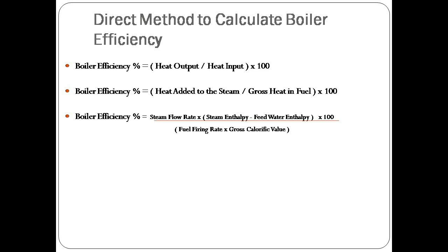As you can see in the third formula, by multiplying steam flow rate with the difference of steam enthalpy and water enthalpy you can calculate heat added to the steam. The gross heat present in fuel or whatever we are supplying to boiler is simply the fuel firing rate multiplied by fuel calorific value.